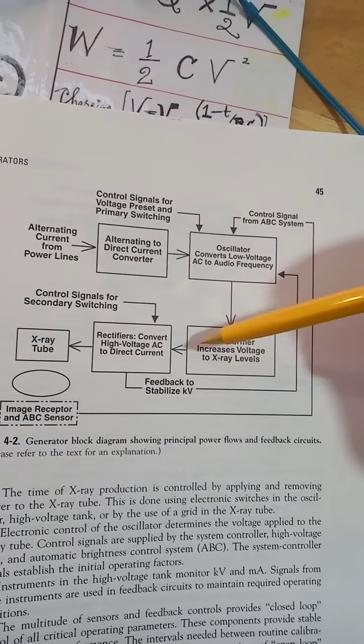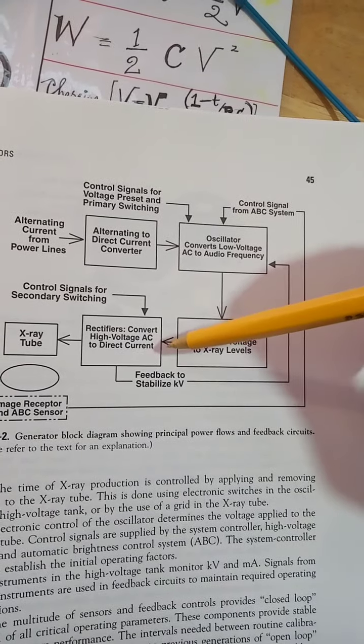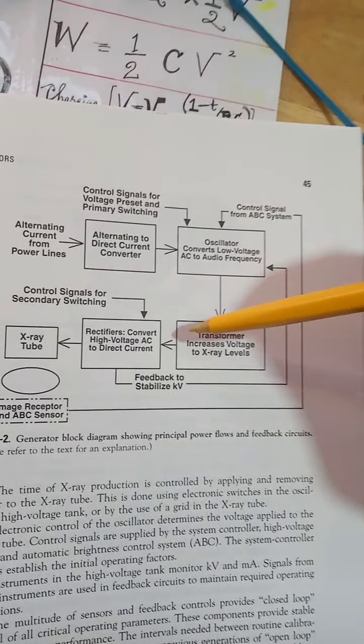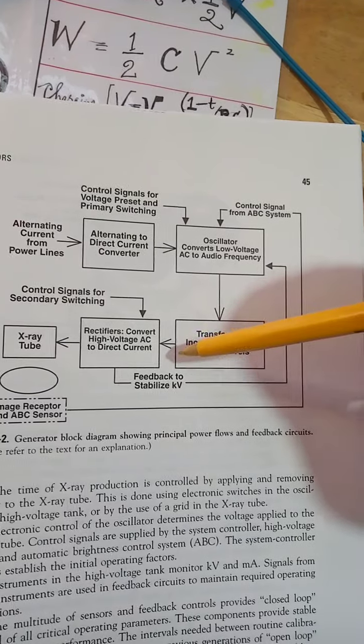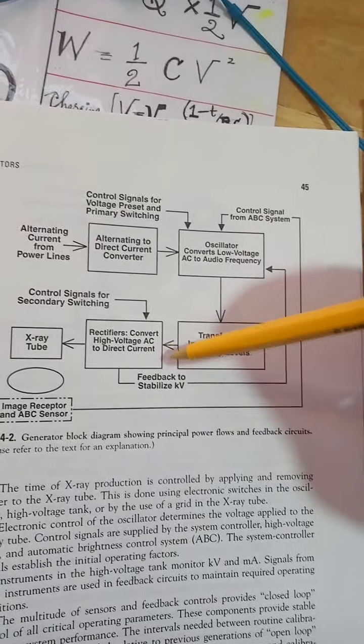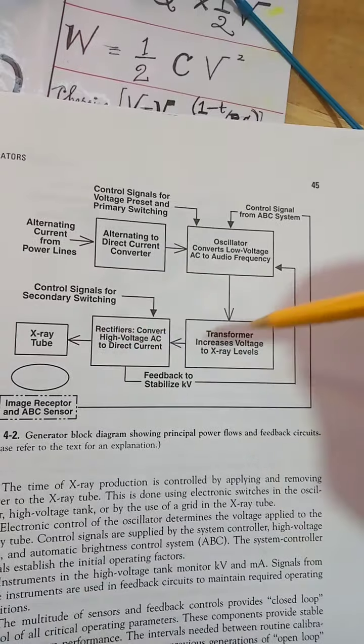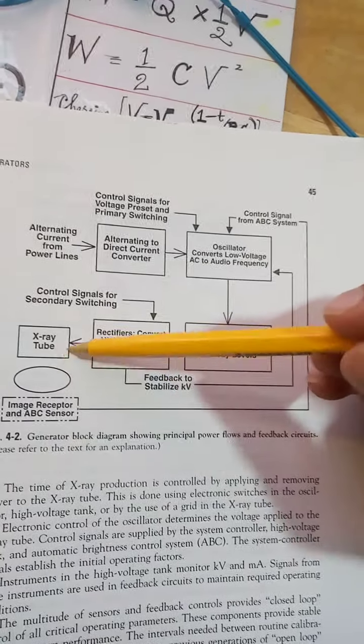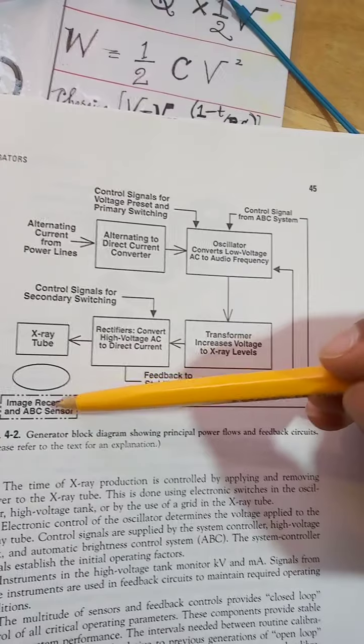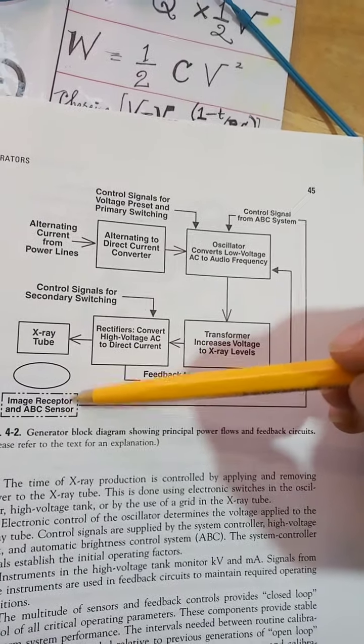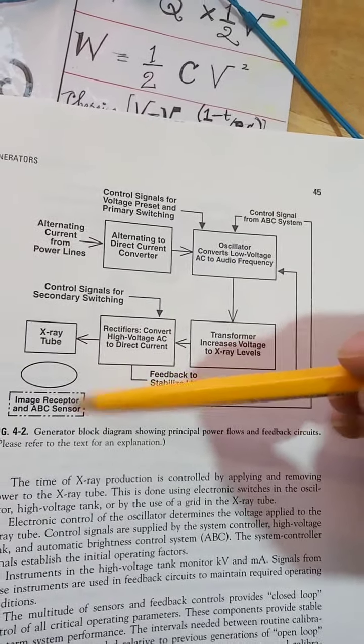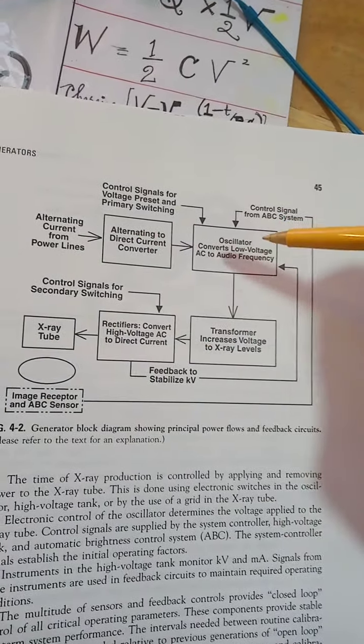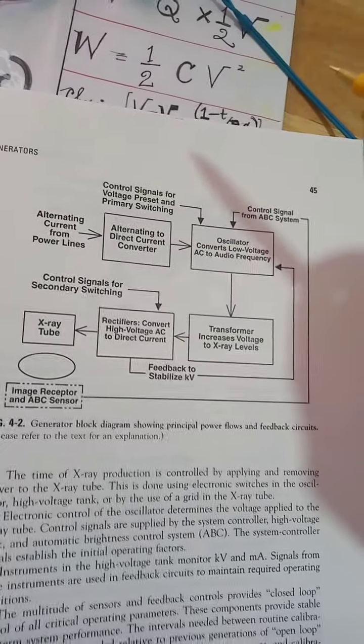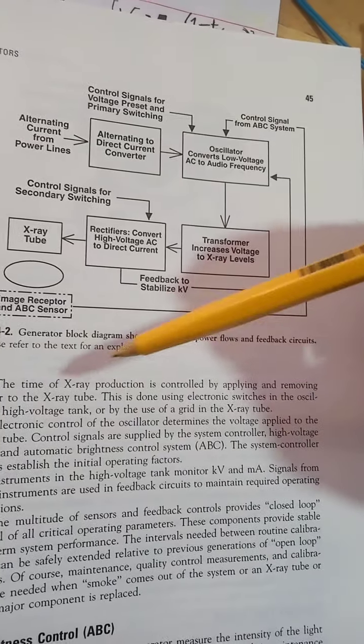And then the rectifiers, the forward bias rectifiers, prevent the backflow of current, and they induce a sense of efficacy and efficiency in the apparatus, and then they push the current and the voltage forward into the X-ray tube, and then the patient gets the X-ray dosage, and then it gets analyzed and imaged by the receptors, and then there's a feedback loop, and then the feedback loop goes all the way to the generator. So the time of X-ray production is controlled by applying and removing the power to the X-ray tube.